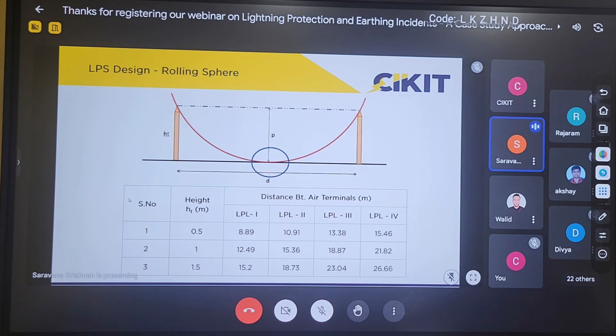We have performed designs for certain site conditions where we used a 5 meter air terminal by providing additional support. For a particular distance I cannot place any air terminal. It is completely shielded, and I cannot place air terminals by providing holes. That is the reason we increased the height to 5 meters, so that the distance is much higher and there is no need for providing air terminals in between. So it is up to the designer to decide the height of the air terminal, and based upon the height, I have to vary the calculations.